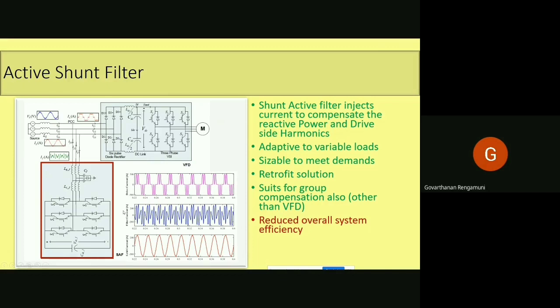But this one needs a 6 pulse converter like this. The IGBT converters is here, and there is an LCL filter. So with this construction and the control circuits, it will be switching the IGBTs in the fashion to inject the current as required. So it is more adaptive based on the load. If the load is varying, according to that, it will correct and adjust its injecting current. So it is scalable to meet demands.